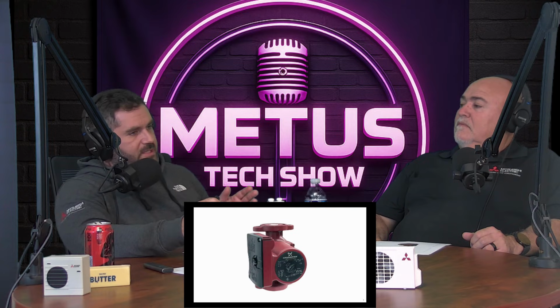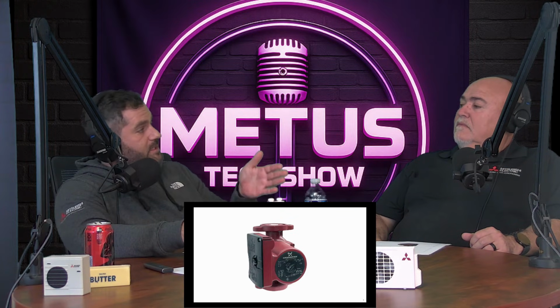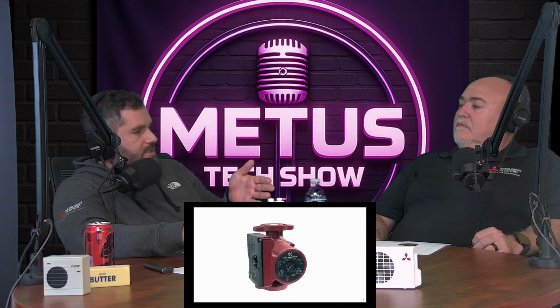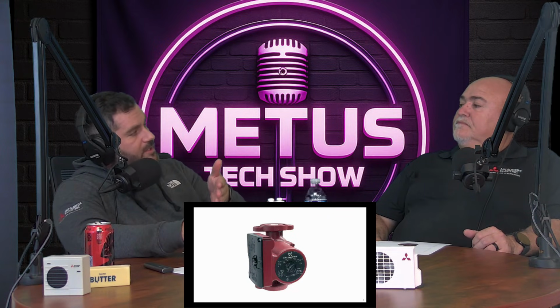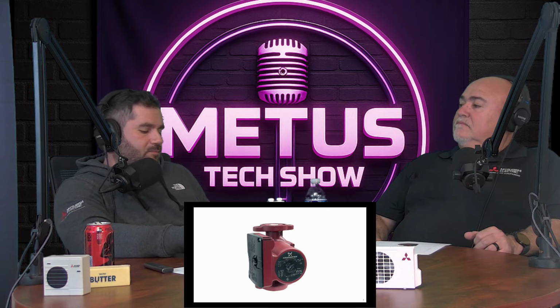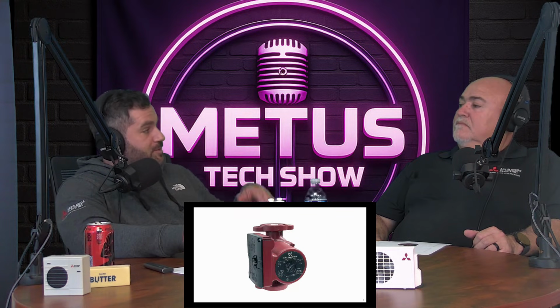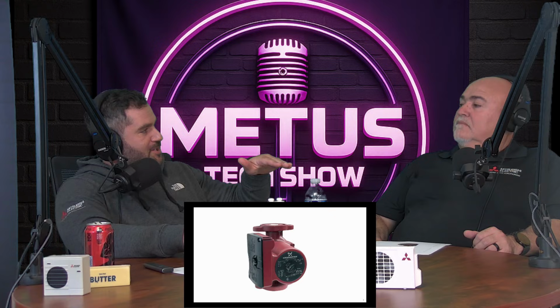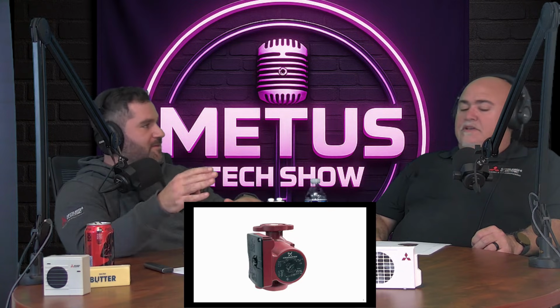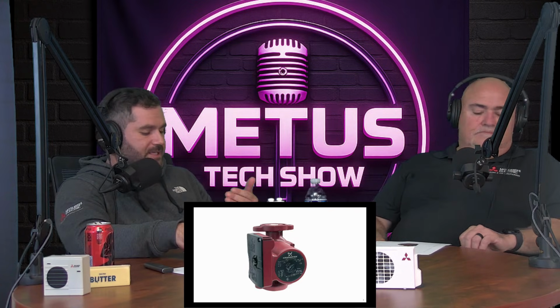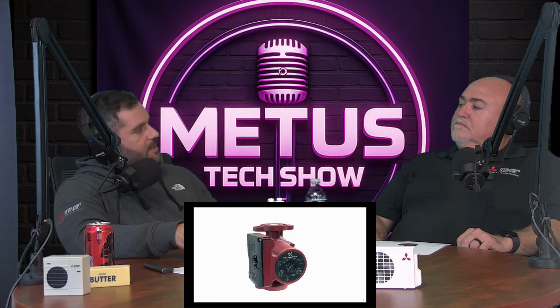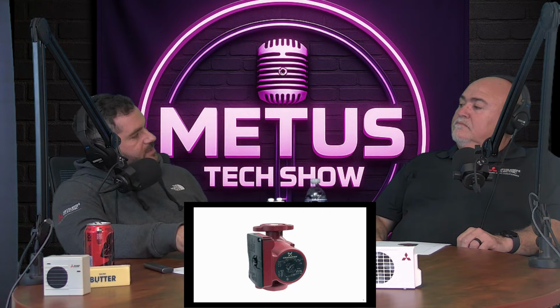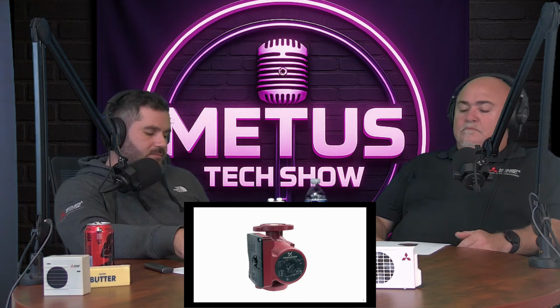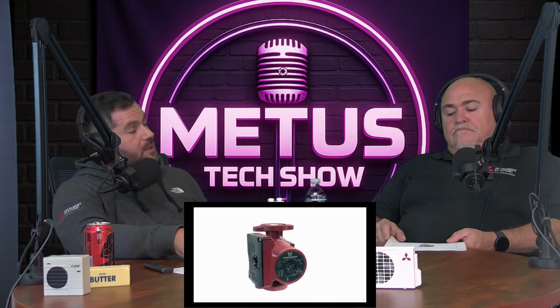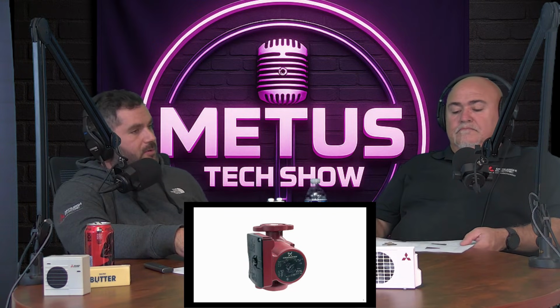And so when it comes to the expansion tank, you want that at the point of no pressure change, which is going to be typically right before this pump, right? So if you put it after the pump, that's when you could run into some potential issues, because it's trying to create a differential pressure, but you just put an expansion tank that maintains a pressure. So if you don't have enough pressure on the inlet side of this pump, it can't actually give head pressure out, and so then you wouldn't have as good a flow through the system. These also come with internal flow checks, which are incredibly important.